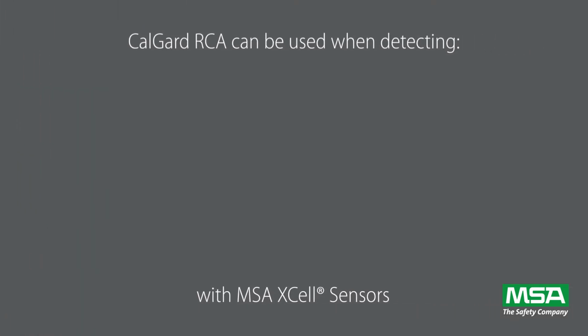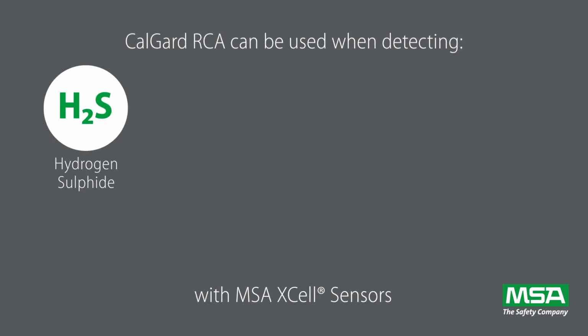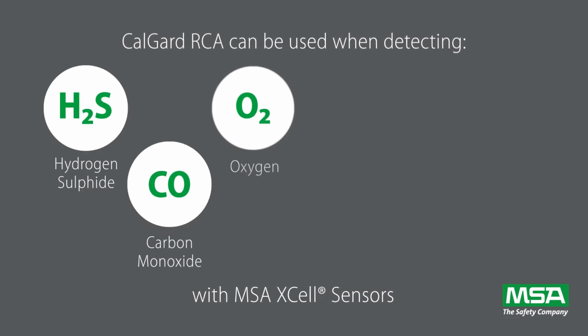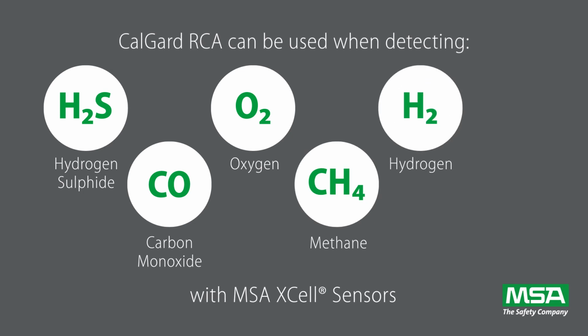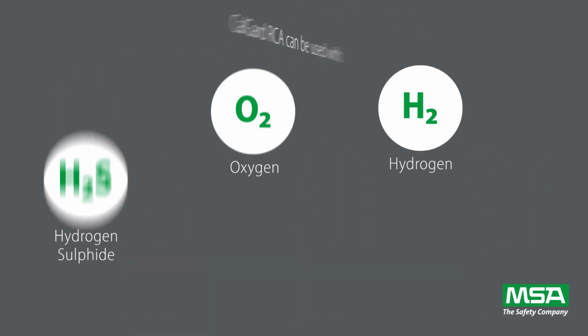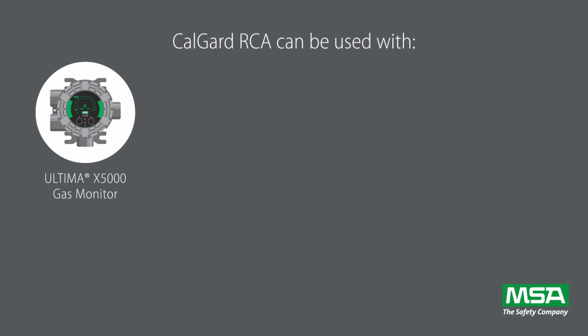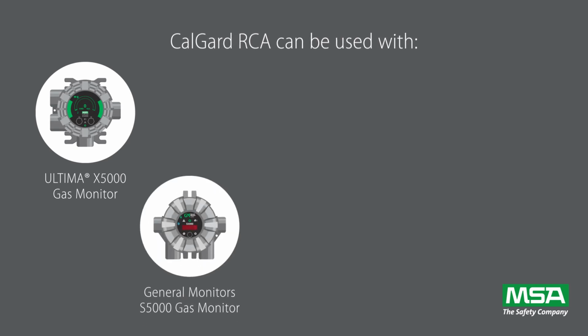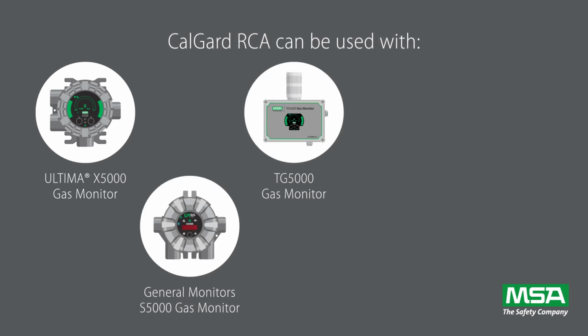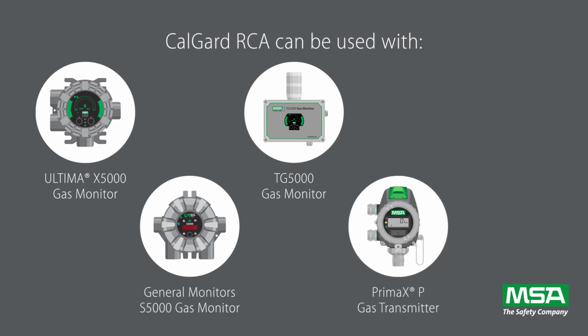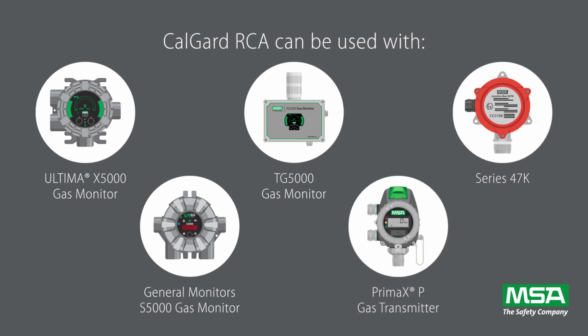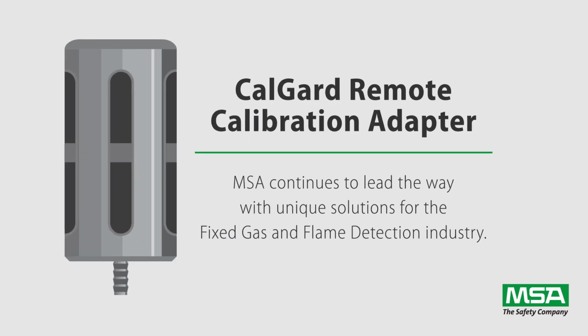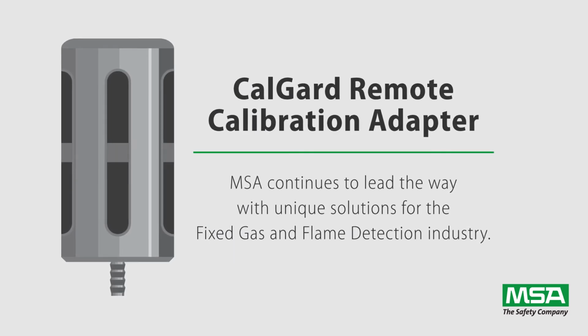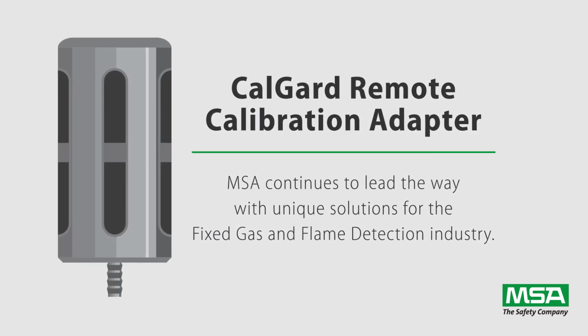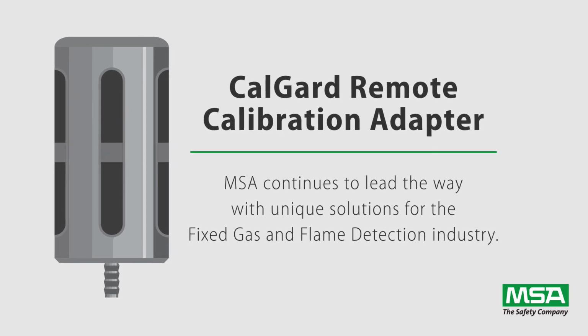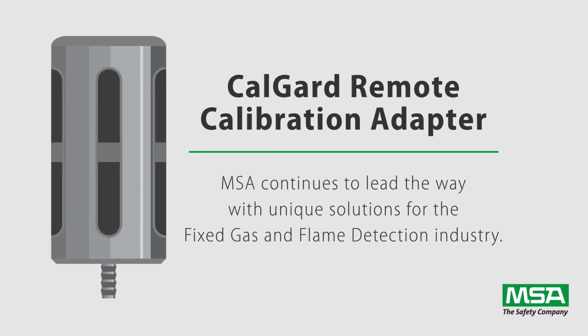The CalGard RCA can be used when detecting hydrogen sulfide, carbon monoxide, oxygen, methane, hydrogen, and propane with XCell® sensors for the MSA ULTIMA X5000, General Monitor's S5000, MSA TG5000, and also on Prima X or Series 47K gas detectors. The CalGard remote calibration adapter is another example of how MSA continues to lead the way with unique solutions for the fixed gas and flame detection industry.